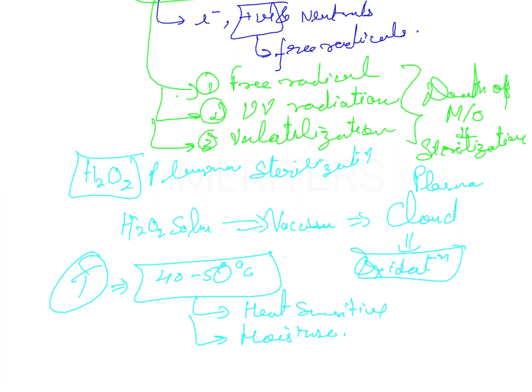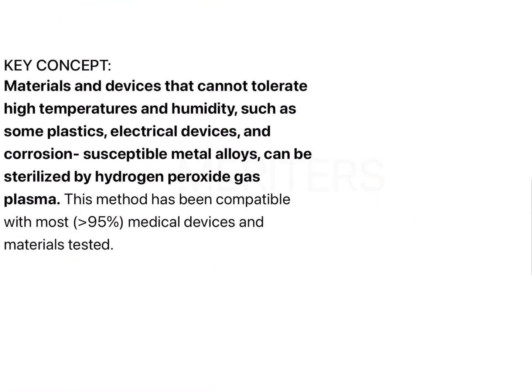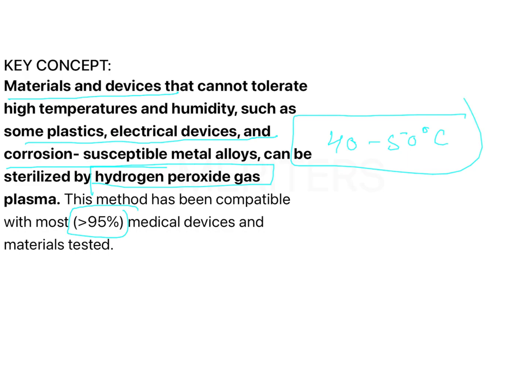The instruments are wrapped prior to sterilization and can then either be stored or used immediately — there is no problem with use after this process. The advantage of the plasma method is the possibility of achieving sterilization at a very low temperature of less than 50 degrees Celsius. Materials and devices that cannot tolerate high temperature and humidity — such as some plastics, electrical devices, and corrosion-susceptible metal alloys — can be sterilized by H2O2 gas plasma. The method is compatible with 95% of medical devices.